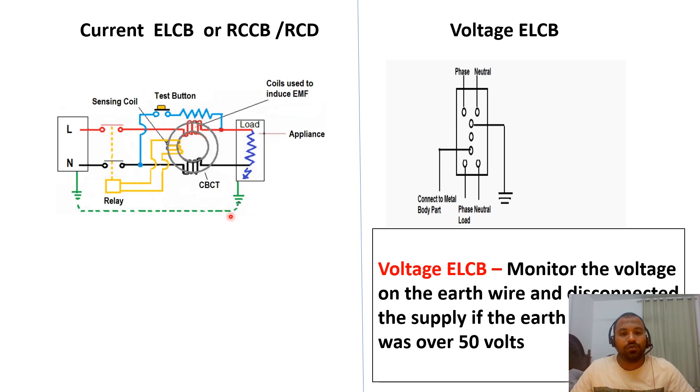There is a current will be thrown through the earth. There is a differential current between phase and neutral. This differential flux will be produced here. This will generate the current in this relay. When this relay senses this current, it will be energized to trip.